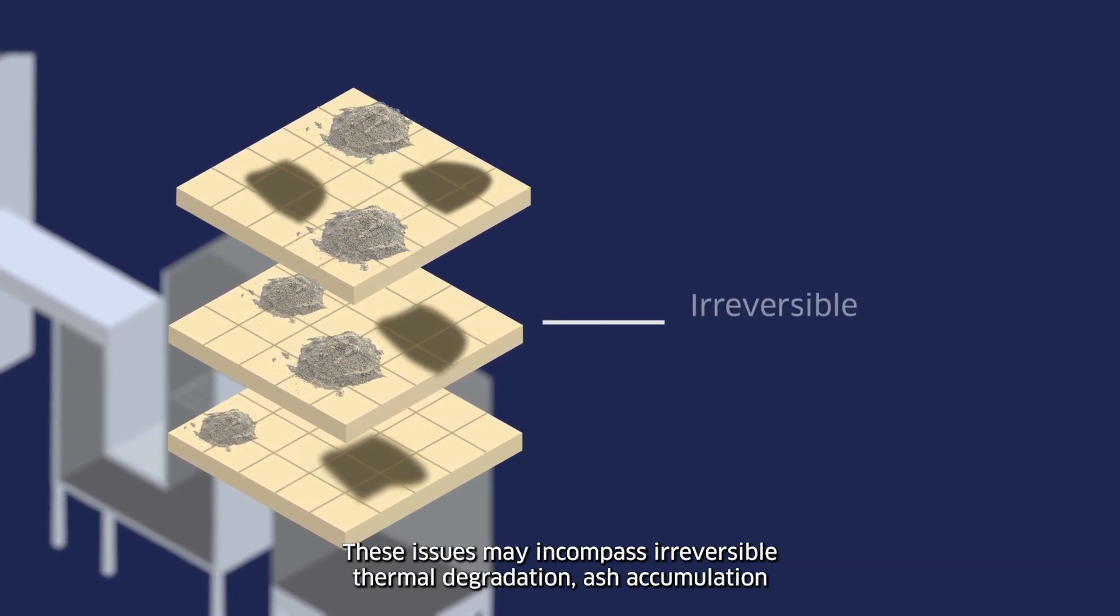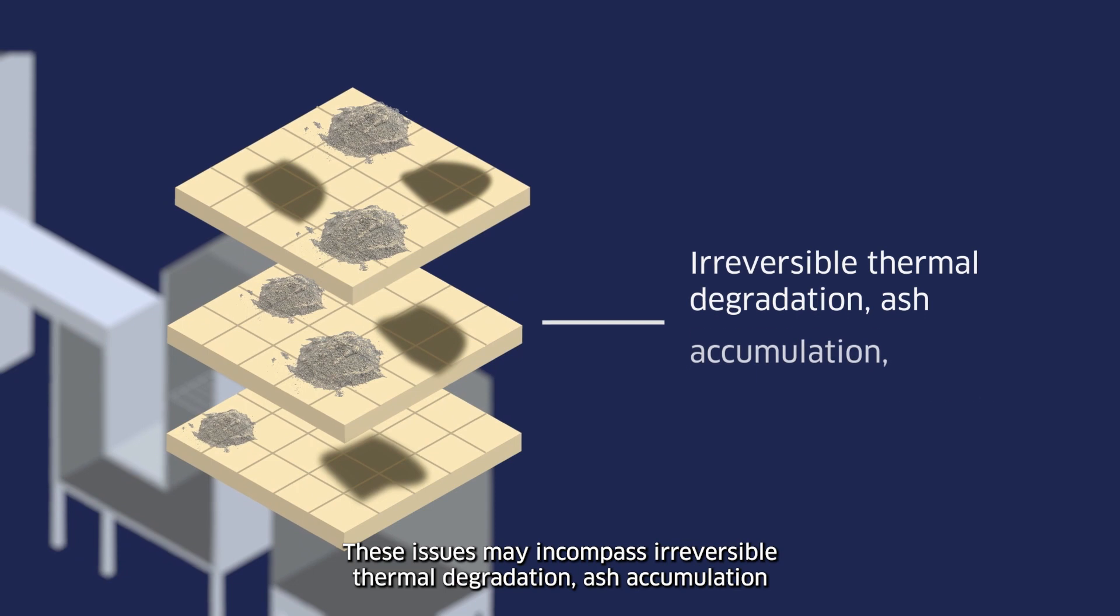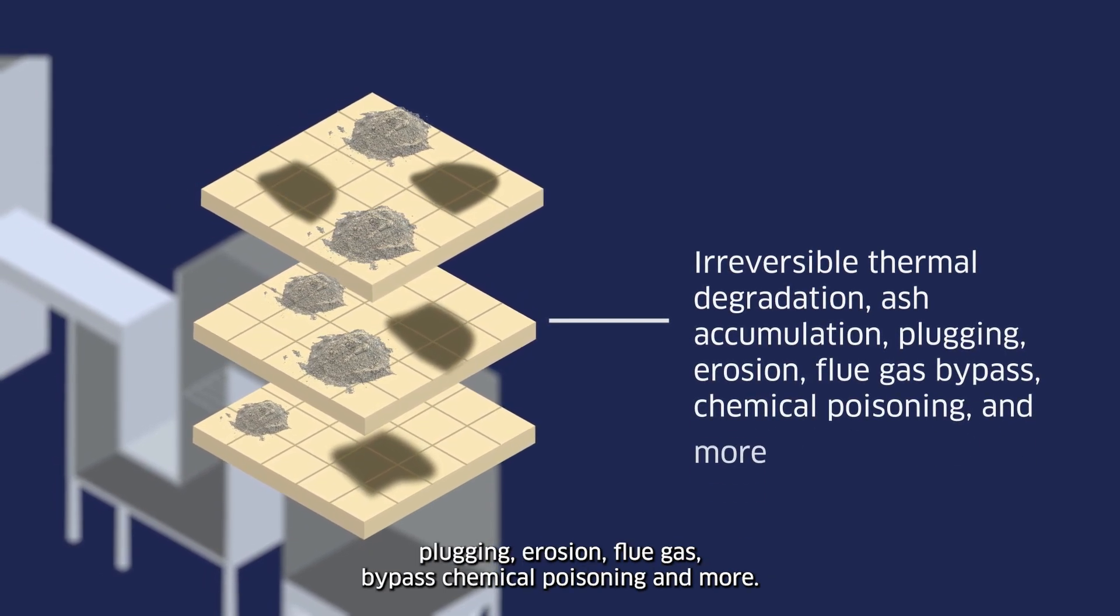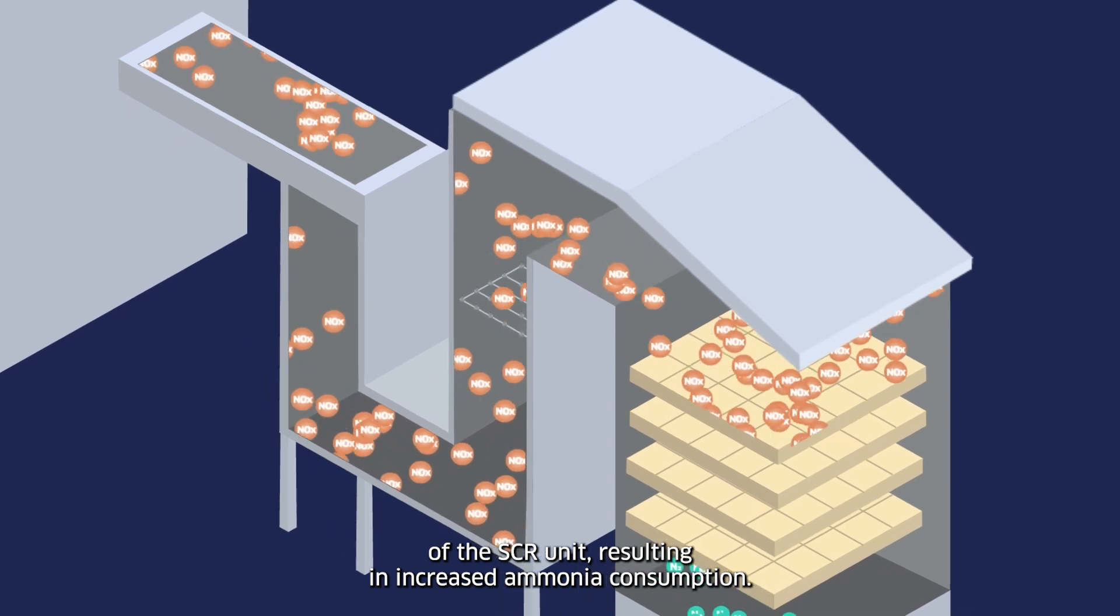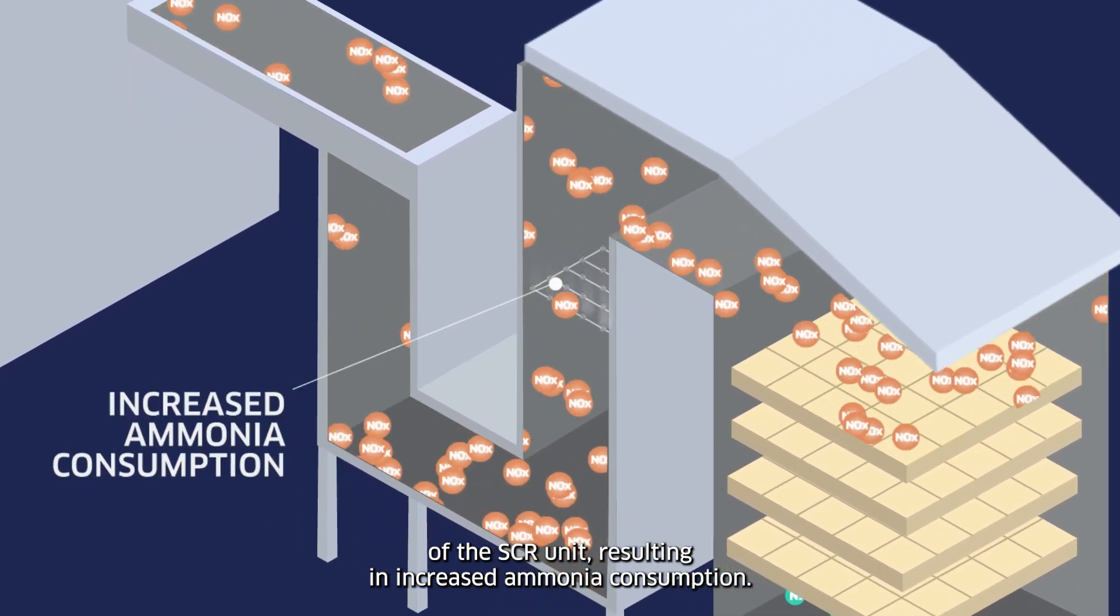These issues may encompass irreversible thermal degradation, ash accumulation, plugging, erosion, flue gas bypass, chemical poisoning and more. These problems directly affect the performance and overall condition of the SCR unit, resulting in increased ammonia consumption.